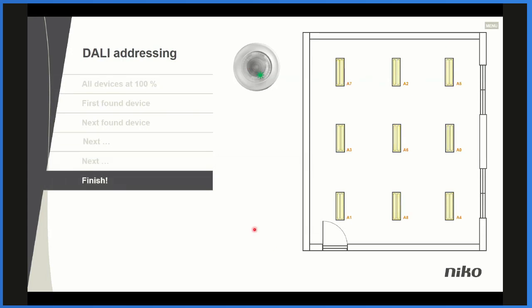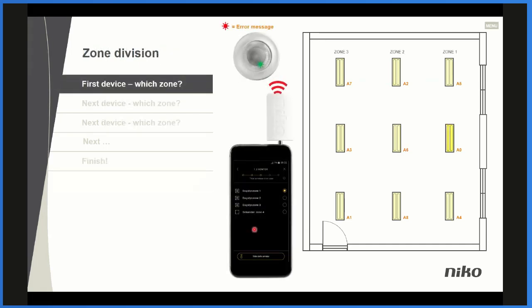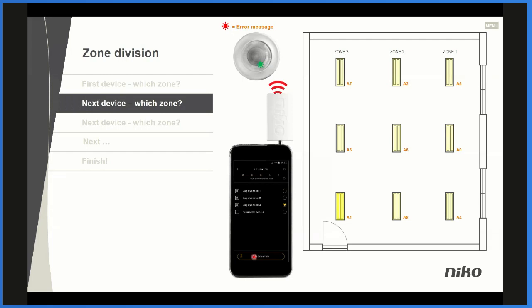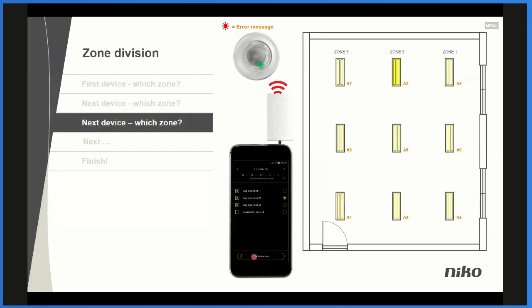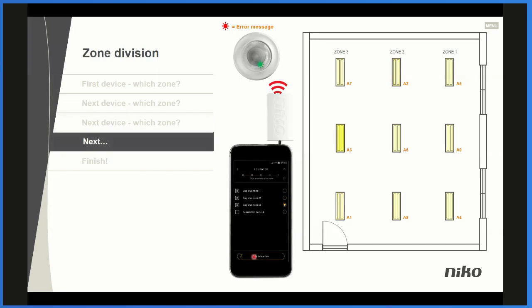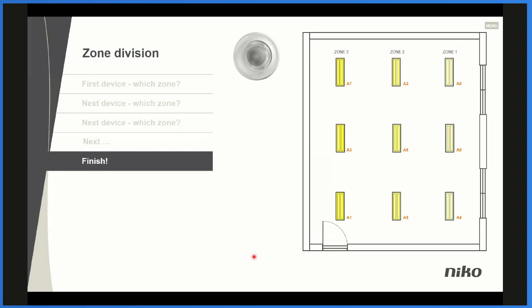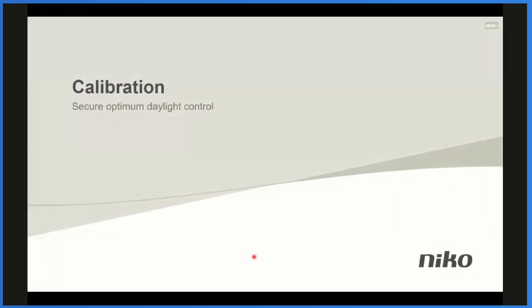When it's all given an address, it's yours to decide in which zone each luminaire is actually mounted, and that is done with the app that we have here, together with the dongle that sends an infrared communication to the detector. You just press in the app, okay, this is in zone 1, and you assign that, and then you go to the next one, and you assign each and every detector, telling it which zone it is mounted in. And when it is done, the detector will show you that now it's done.